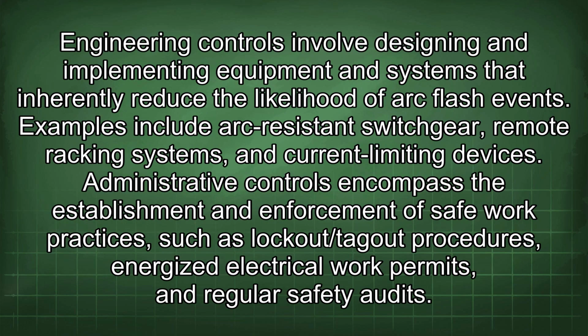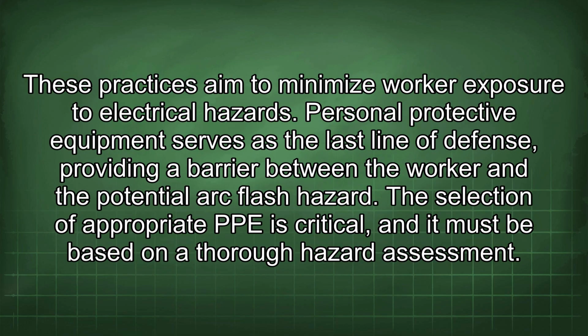Engineering controls involve designing and implementing equipment and systems that inherently reduce the likelihood of arc flash events. Examples include arc-resistant switchgear, remote racking systems, and current-limiting devices. Administrative controls encompass the establishment and enforcement of safe work practices such as lockout/tagout procedures, energized electrical work permits, and regular safety audits. These practices aim to minimize worker exposure to electrical hazards. Personal protective equipment serves as the last line of defense, providing a barrier between the worker and the potential arc flash hazard.